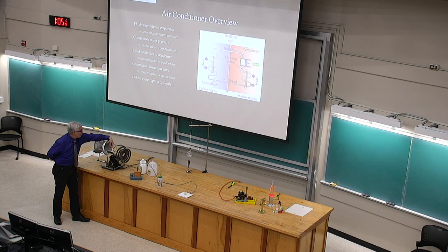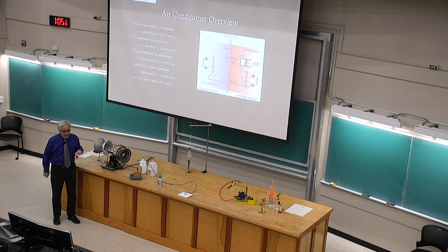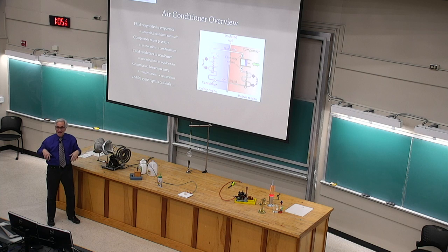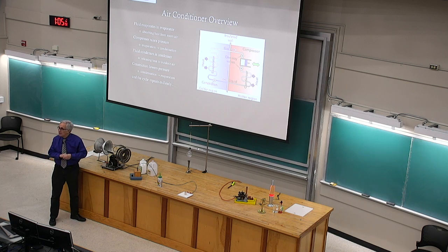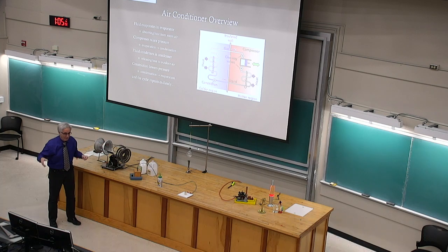It goes through a valve, that constriction that's up there on the drawing, which is just a device that uses things familiar to us, viscosity and so on in the liquid, to allow the liquid to go from high pressure liquid to suddenly low pressure liquid. The liquid enters a chamber, a big cavity from its perspective, where the pressure is low.